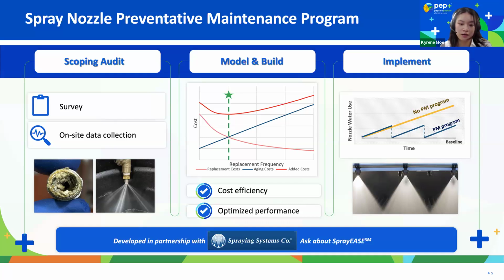With this performance data, you can put together a model that shows exactly what the optimal replacement frequency is. The longer you wait to replace, the more water you use and the higher your cost, but also the lower the annual cost of each replacement is. The model analyzes that data and looks for the intersection of those two trends based on your specific operational data, and that becomes the replacement frequency that works best for you.